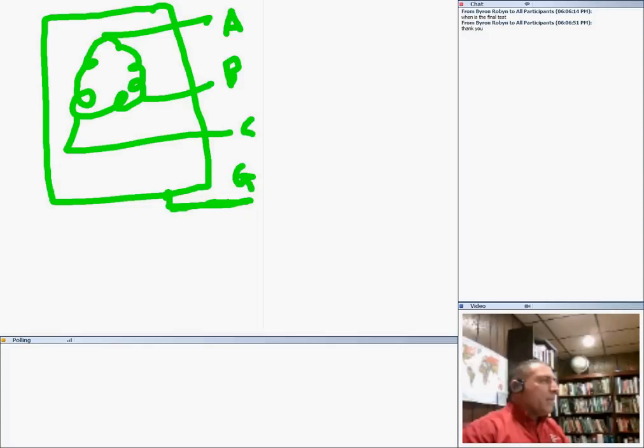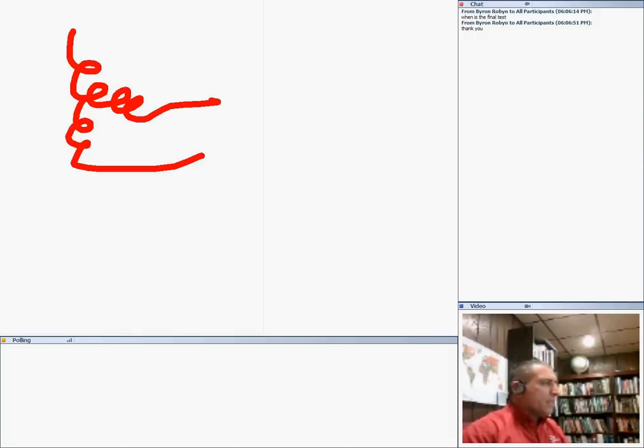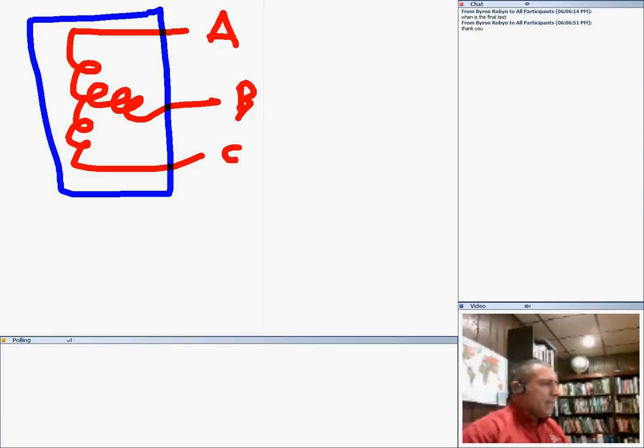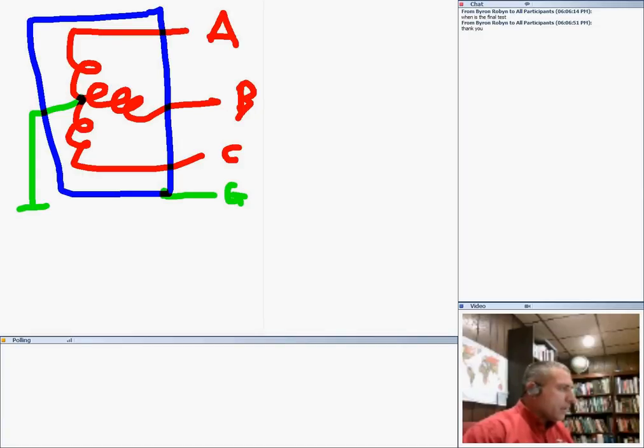When we say grounded system, we mean one of the phases or windings. For example, if I go right into the middle of this winding and take it directly to my earth, the system is grounded. Another example: here's a delta, here's a Y. You guys are familiar with the Y, with phases A, B, and C. I'm going to go to my transformer frame and take this one as an equipment grounding conductor. Is this system grounded? This system is not grounded. Why? Because to make this system grounded, you have to go to the center here and take this one directly to Mother Earth. Now this system is grounded. Can you see what the words system grounded mean?